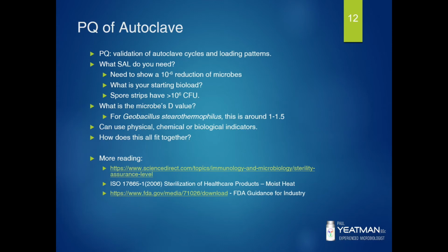You want to consider whether you use physical, chemical or biological indicators. The physical indicators would be the thermocouples during the autoclave validation, and the biological indicators could be spore strips or spore solutions depending on the product you're testing. So when I've validated or revalidated autoclave loading patterns, I've used biological indicators in the form of strips for an autoclave cycle within the lab, and spore solutions when I have assisted production in validation of their cycles.